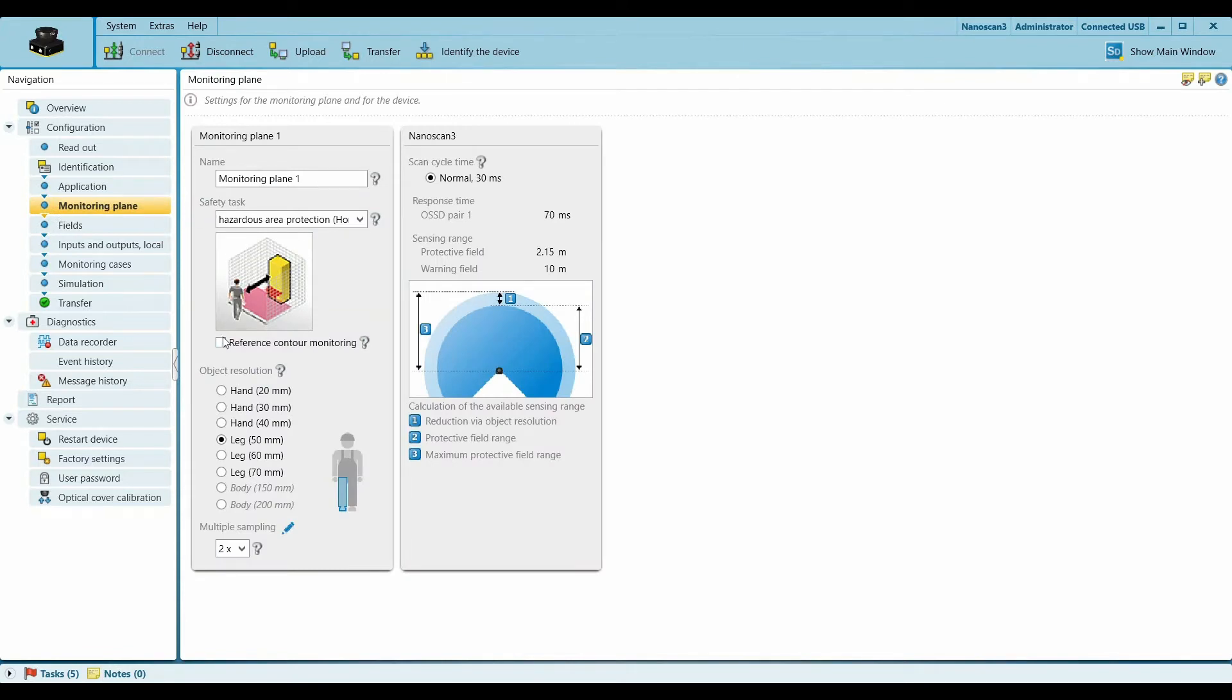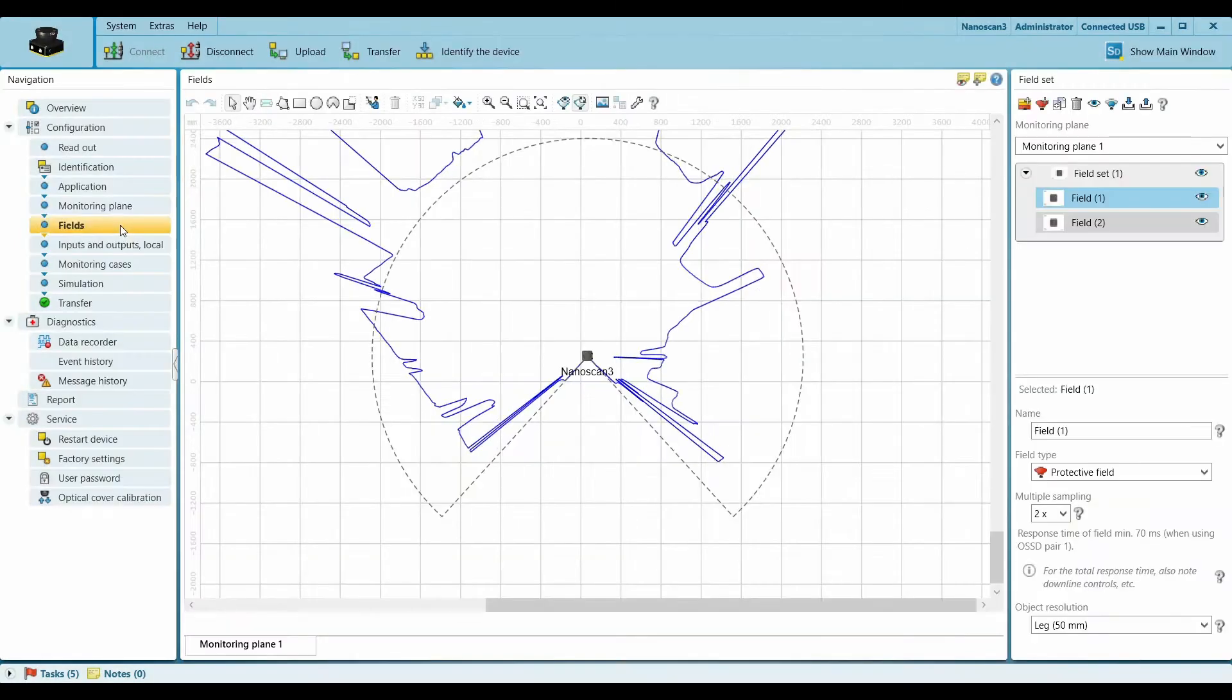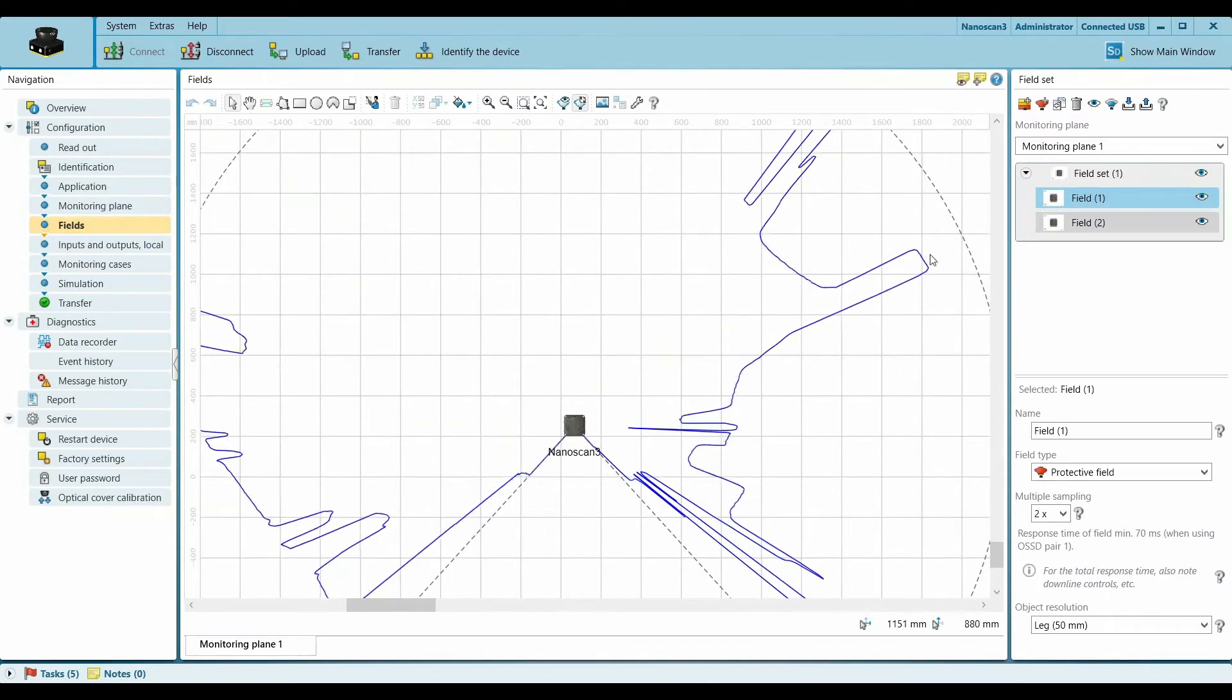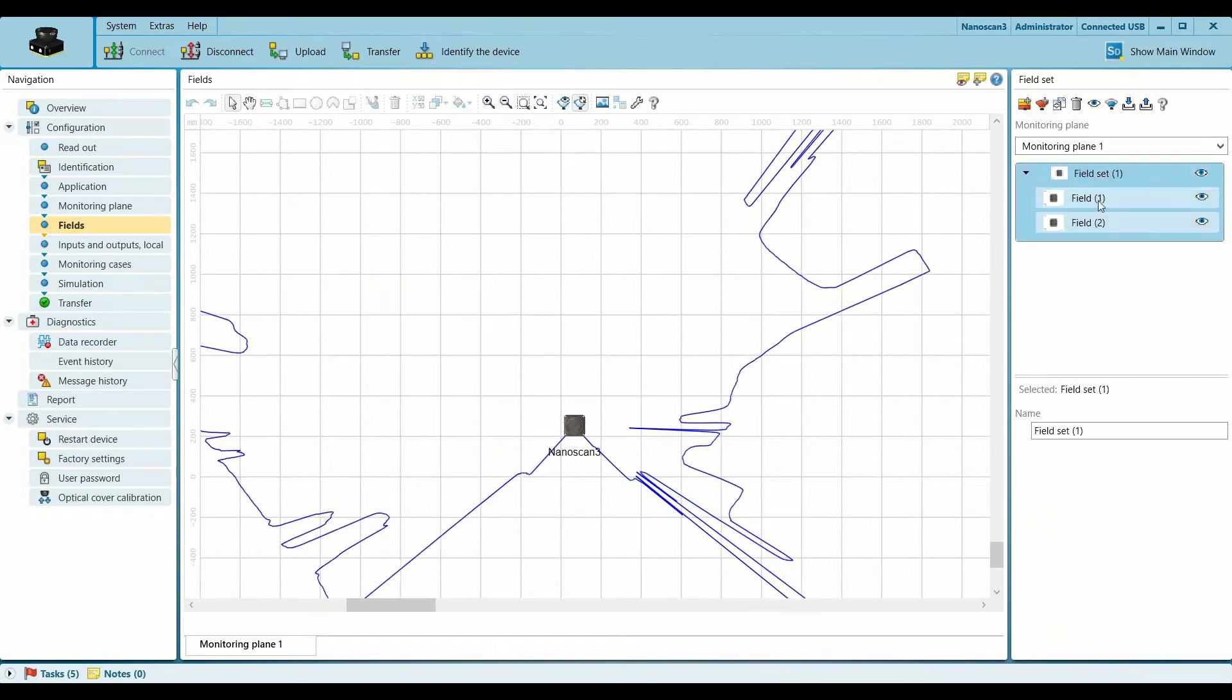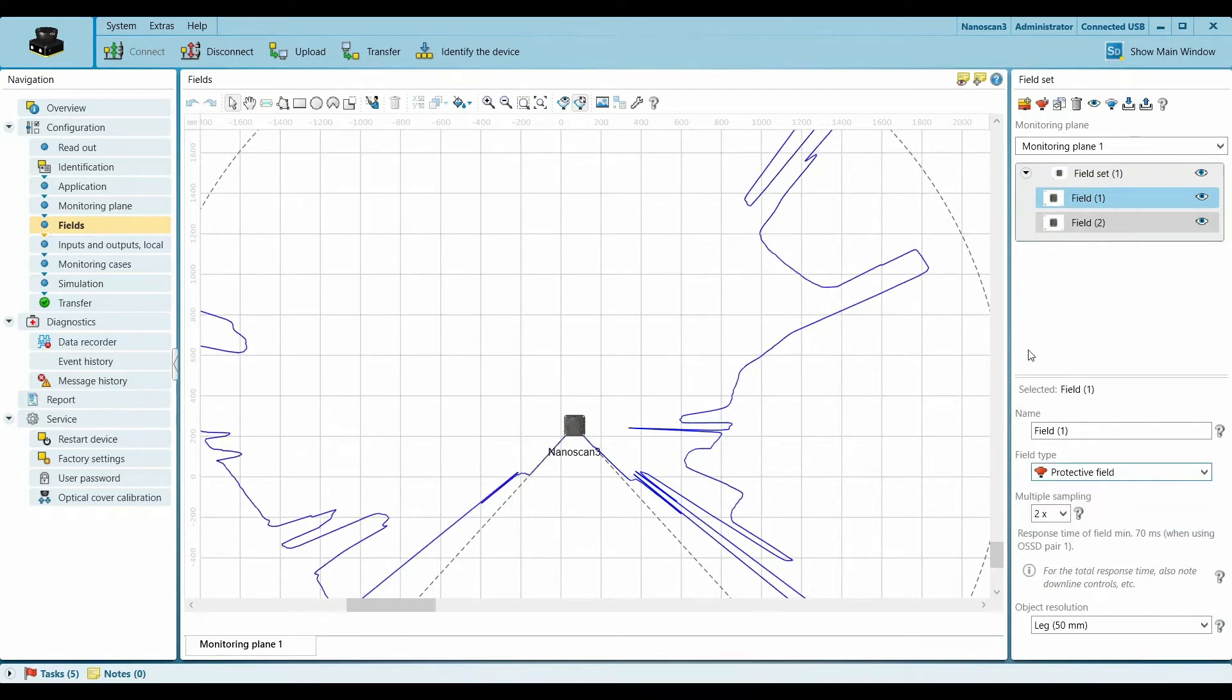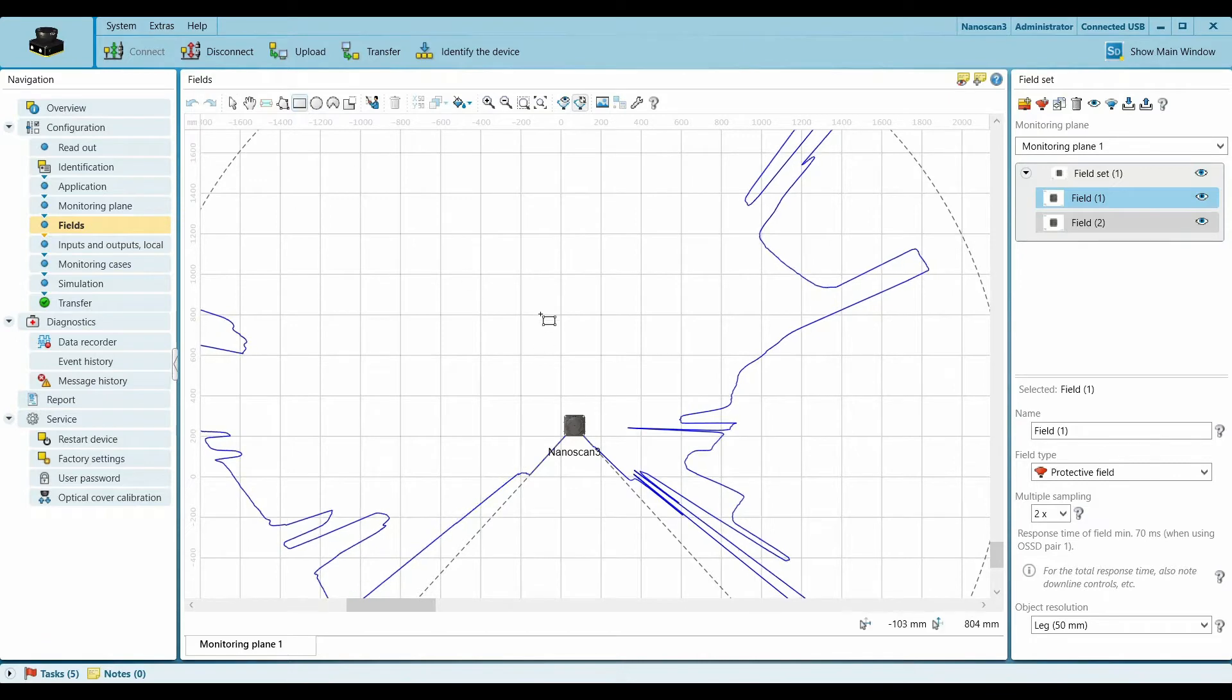In this we actually define what we are trying to detect. In my case I'm detecting legs, 50 millimeter resolution. Downstream we have Fields. What happens in Fields is that we actually define our zones here. On the right side you will see one field set which has two fields. In our case we have a robot and I'm using a protective field to safeguard it, and I'm using a rectangular tool to define my zones.